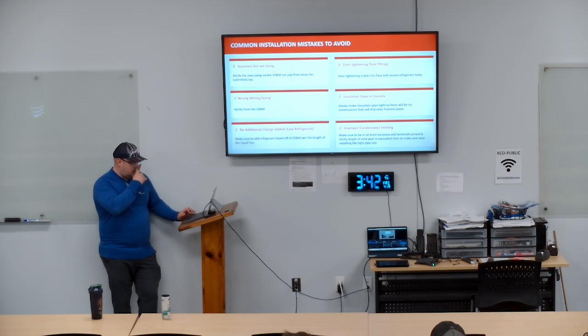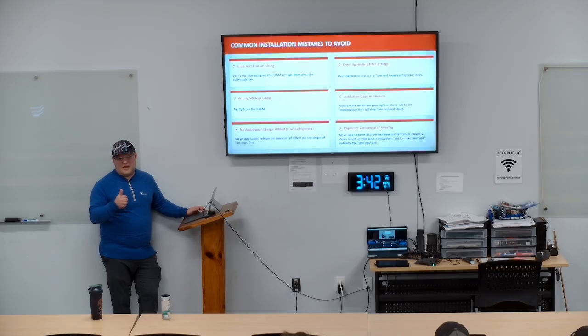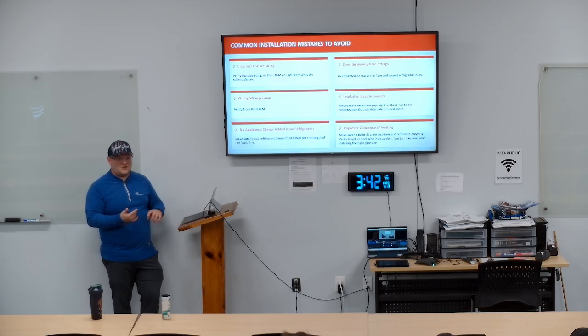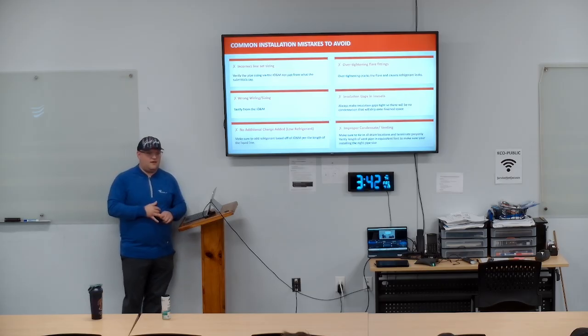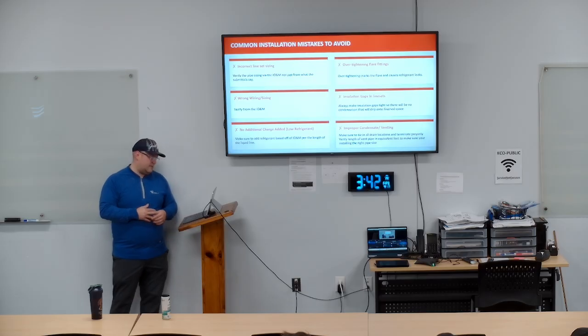So common installation mistakes to avoid. Okay. Incorrect line sizing, see it all the time. And if it happens, I'm telling you, 9 times out of 10, you're ripping it out. We've had instances where it's like, oh, I ran this size, it doesn't work. If I run a different size, I'm losing efficiency, I'm losing the capacity of that unit. So if I have a 5-ton unit and I run too small of a line set, it's only going to give them 3 tons. Well, now I'm screwing the customer because it's going to run longer. It's never going to satisfy. If a manufacturer sees that, they're going to say, yeah, it's because you did your job wrong. Pull it out and start over. And that's what we got to do.